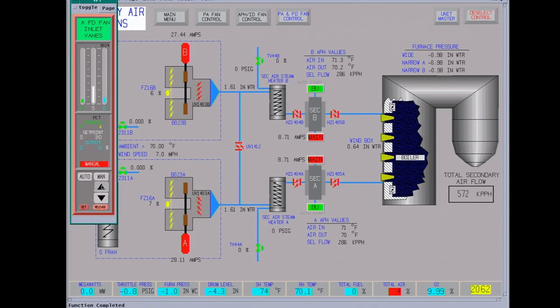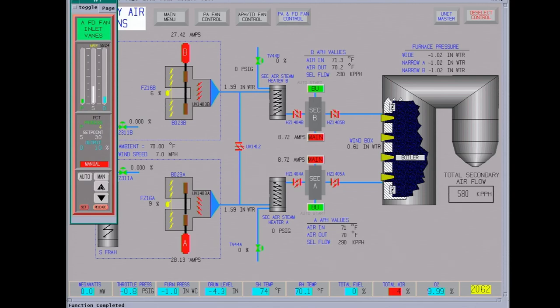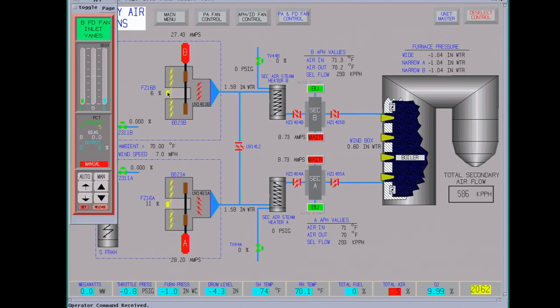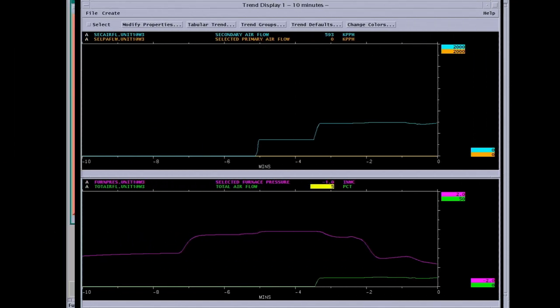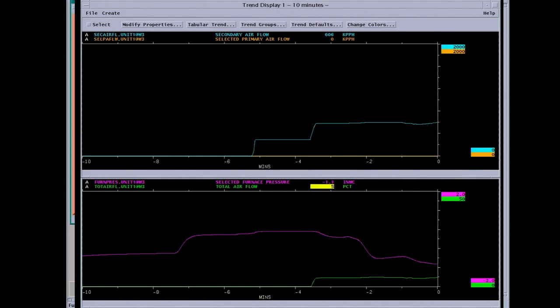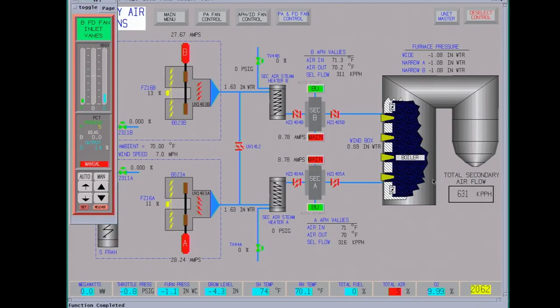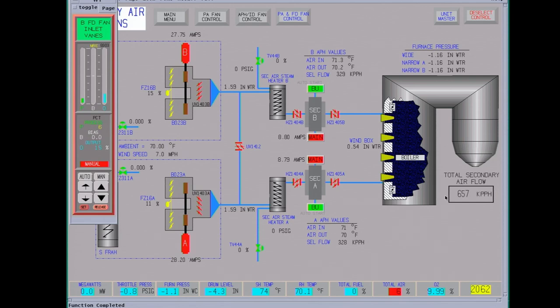This will purge for 5 minutes. That's fairly typical. A lot of furnaces have a certain time frame, and it's somewhere around there with so much air flow. The ID fans are catching the increased air flow. Over here we have the total flow in 1,000 pounds per hour. So it's flowing about 600,000 pounds per hour of air secondary.